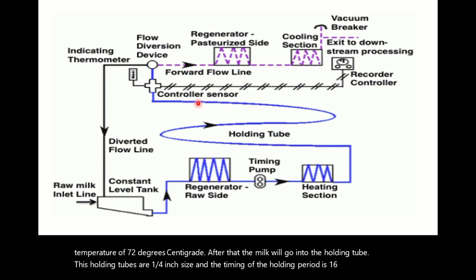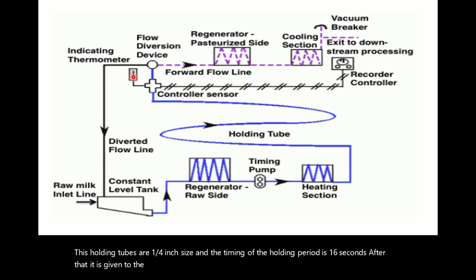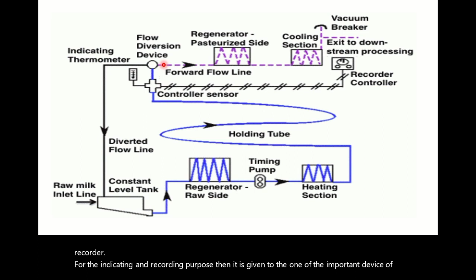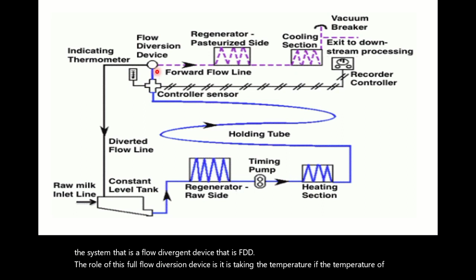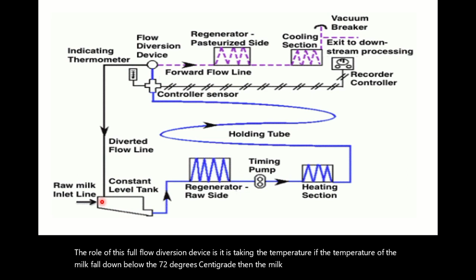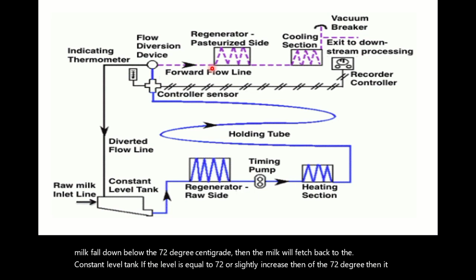After that, it is given to the indicator, that is a thermometer indicator, and it is also given to the recorder for indicating and recording purposes. Then it is given to one of the important devices of the system, that is the flow diversion device, FDD. The role of this flow diversion device is that it is checking the temperature. If the temperature of the milk falls below 72 degrees centigrade, then the milk will be sent back to the constant level tank. If the temperature is equal to 72 or slightly higher than 72 degrees, then it passes to the regenerator pasteurization side.